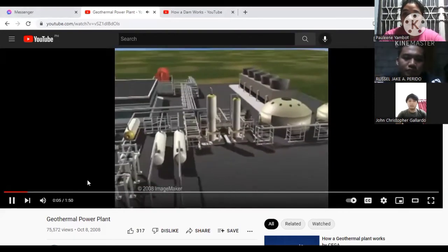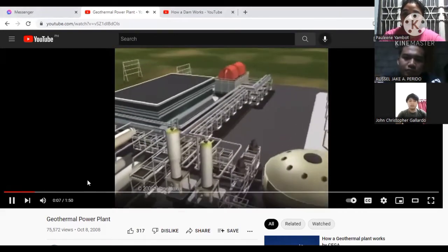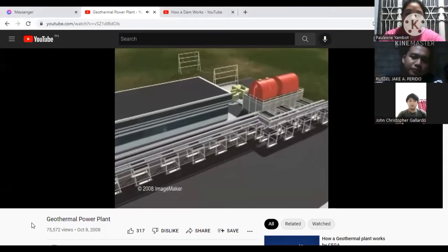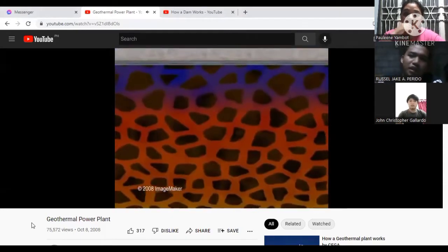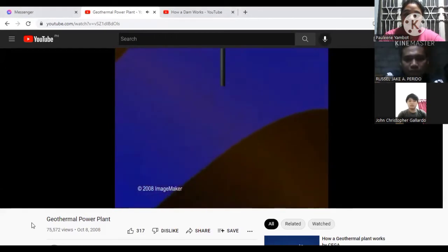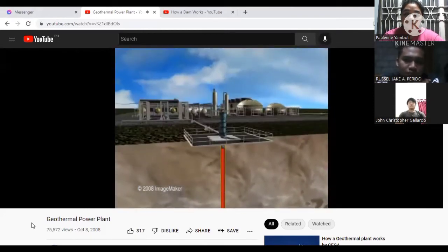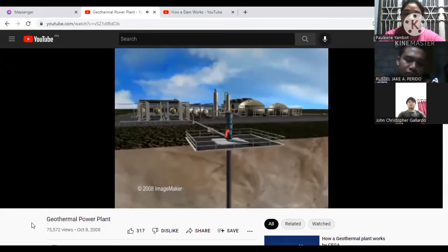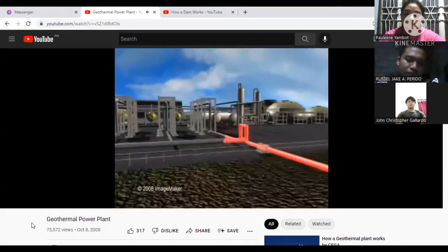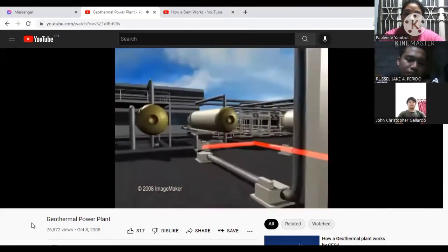Geothermal energy gives us a steady supply of electrical power with minimal environmental impact. Here is the basic process: water in underground reservoirs is heated to high temperatures by magma. Production wells drilled up to 10,000 feet below the Earth's surface tap into this hot fluid. Under its own pressure, the fluid flows through these wells toward the surface. As it travels, the pressure lessens, causing a small amount to become steam. Together, the hot fluid and steam move through a surface pipeline to a wellhead separator, where the pressure is reduced.